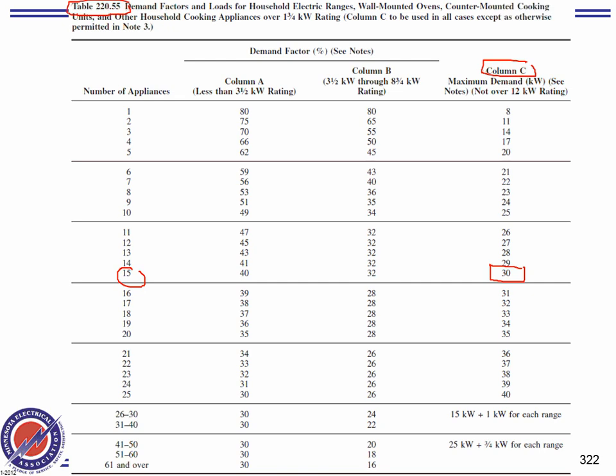Default is always C. Are any of my ranges under A, size-wise? Is any one of them less than 3 and a half? If the answer is yes, then you apply the demand factor to these ranges which are under A. The second question you ask yourself: are any of my 15 ranges within the range of B? If your answer is yes, you apply B to all the ranges that go under B. And then you add these two together. Add them up, and then you compare the answer with what you got under C.